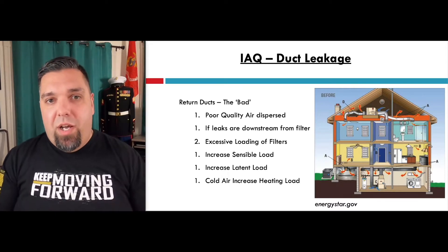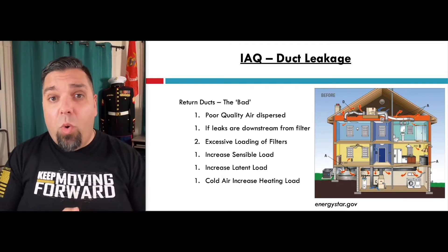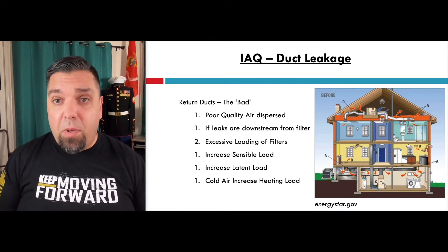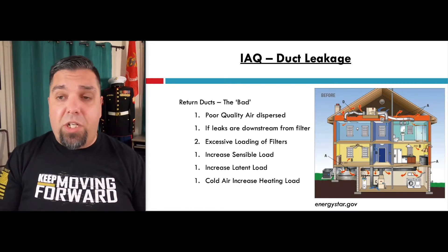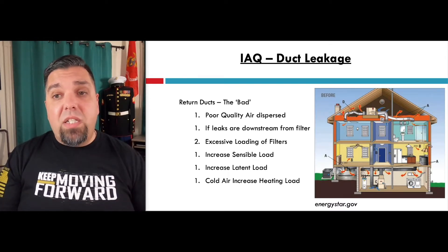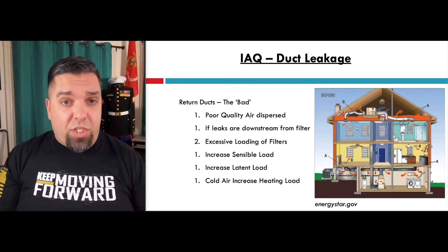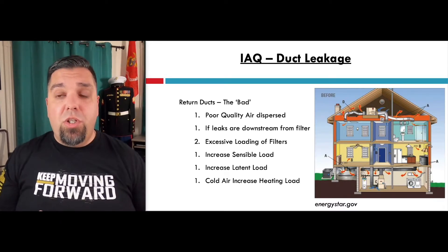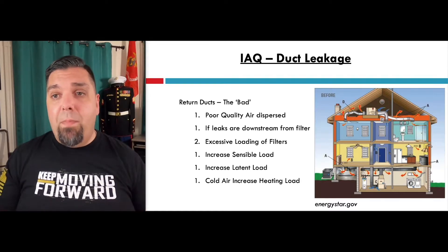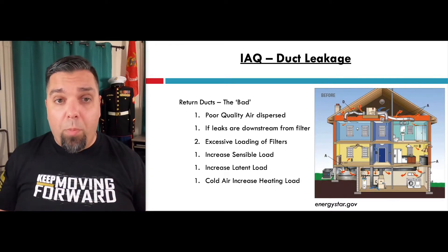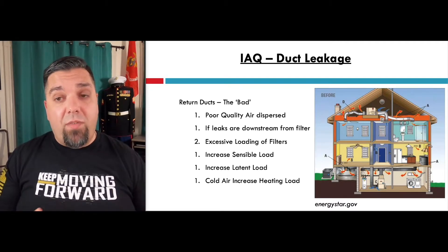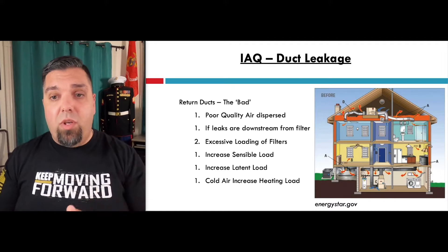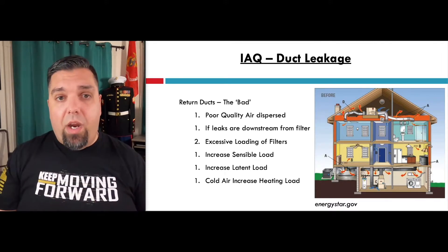So if you have poor quality air and you disperse it throughout the whole home because you have leaky return ducts pulling from the attic — like here in the picture on the right — you're going to make a bad system worse. If you install a high-efficiency variable speed system, you'll just slow that air down and make it worse for the home. If leaks are downstream from the filter, the air isn't going to be filtered. Return leaks at the unit will suck all that attic air in.